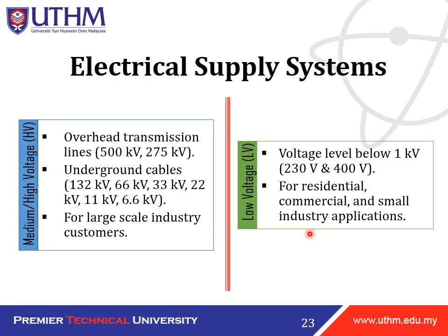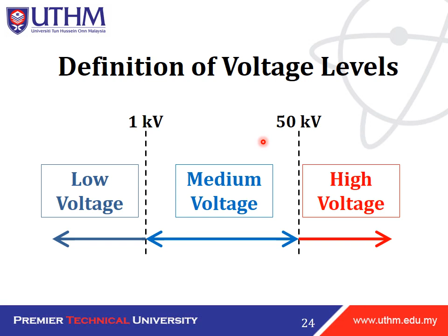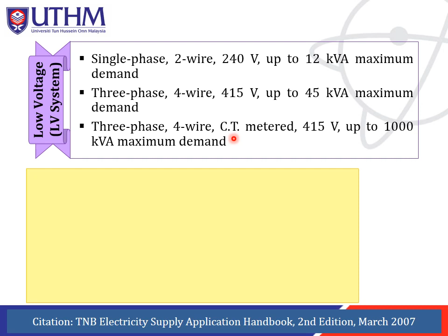So, the definition of voltage level can be divided into low voltage, medium voltage, and also high voltage. From this figure, we can say that low voltage is defined by voltage below 1 kilovolt. And then for medium voltage, we can define it as voltage between 1 kilovolt and 50 kilovolts. High voltage is voltage more than 50 kilovolts. Okay, a low voltage system can be single phase, 2 wire, 240 volt up to 12 kVA maximum demand, or 3 phase, 4 wire, 415 volt up to 45 kVA maximum demand, or 3 phase, 4 wire, C.T. metered, 415 volt up to 1000 kVA maximum demand.